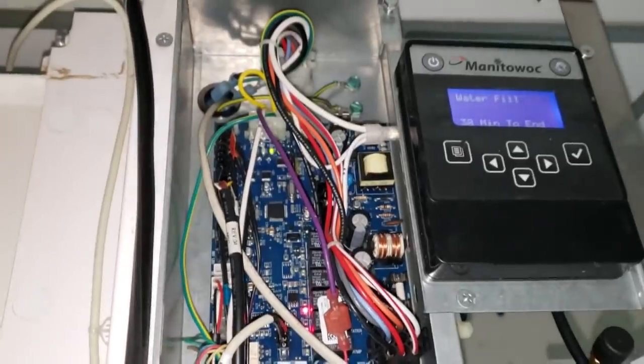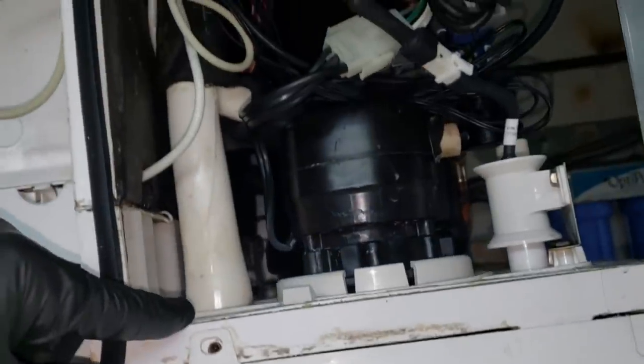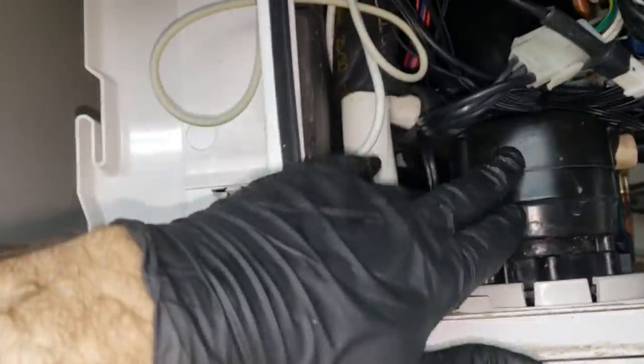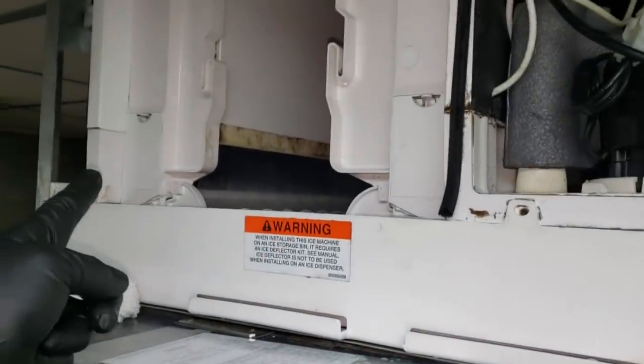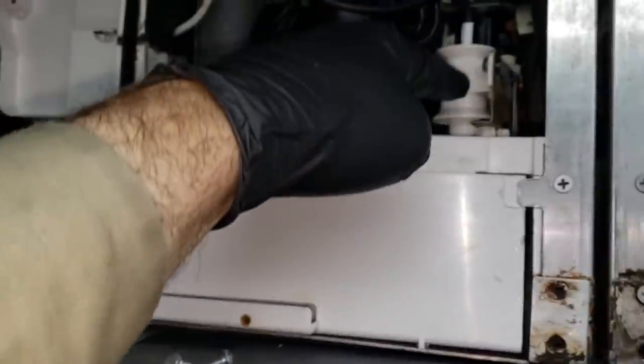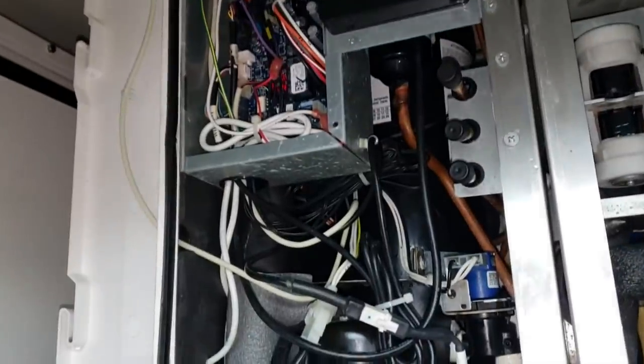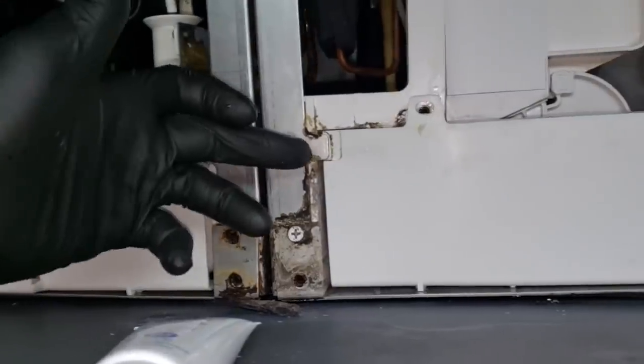Okay, so we've changed the thickness probe, changed the water level sensor, cleaned the dump valve, cleaned everything else. On this machine, we changed the water inlet valve, thickness sensor, water level probe. I have a feeling we're going to have to change some thermistors, but we'll get to that in a minute. We're running ice machine cleaner through it one more time, now that we've got it all assembled. And again, you can only do so much, can't get this stuff up. So we're running the ice machine cleaner through it, and when that's done, we'll run sanitizer and then do a sanitizing on the whole thing in the bin too. See all the stuff down at the bottom. And then we'll start them up and diagnose from there.